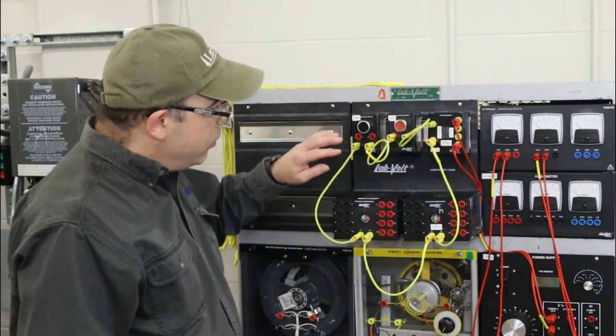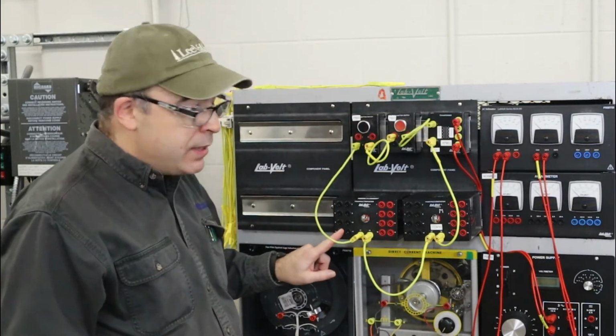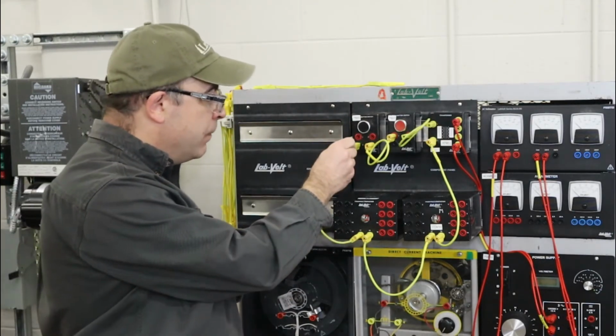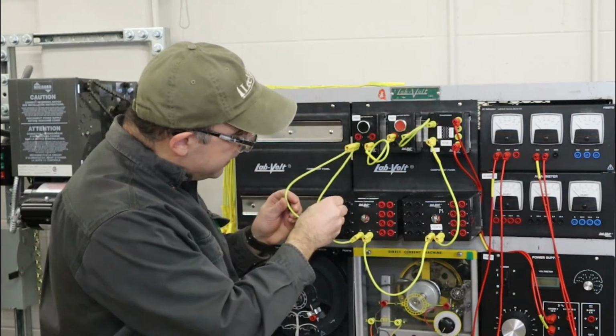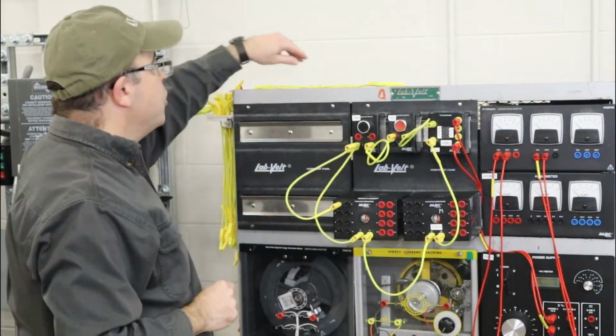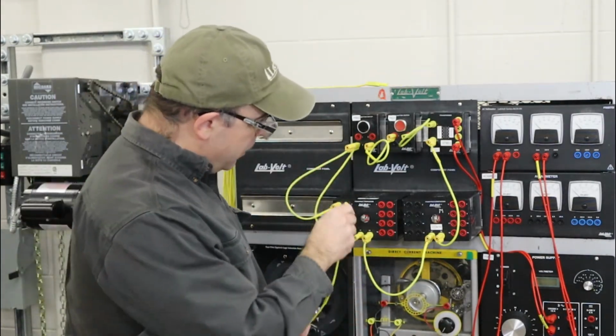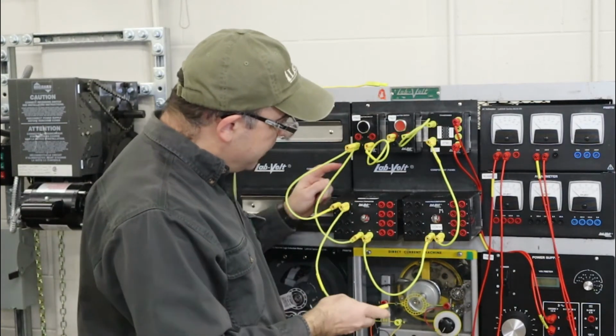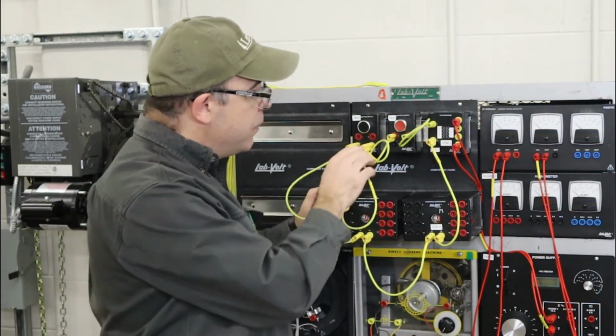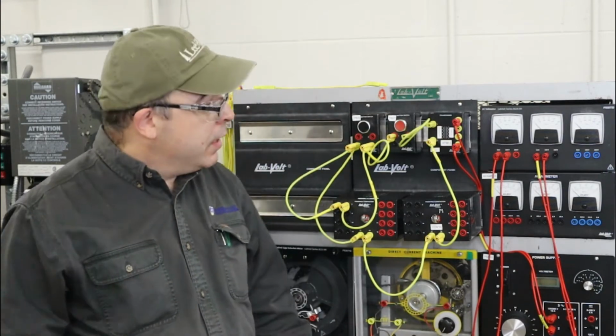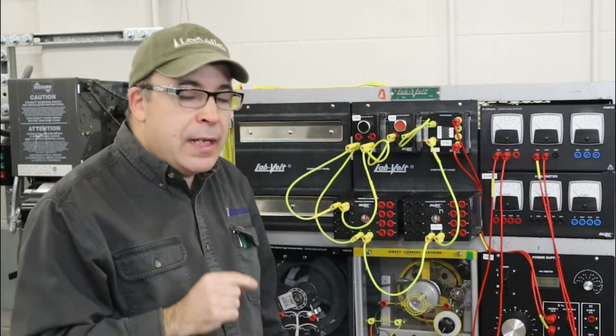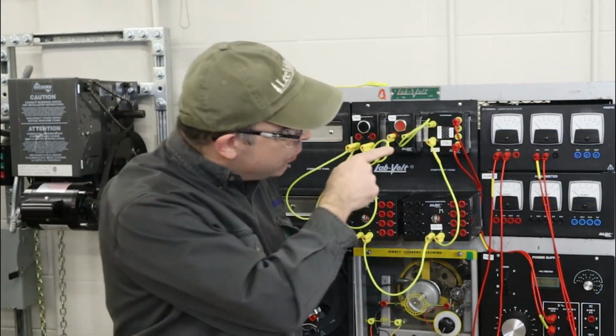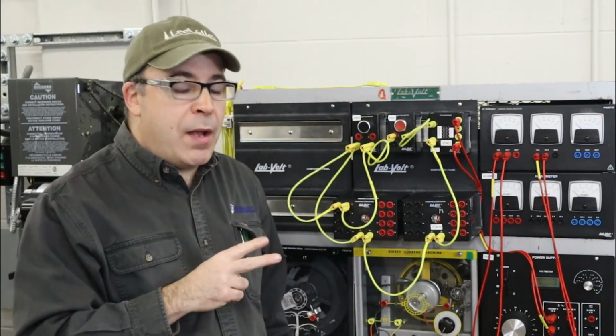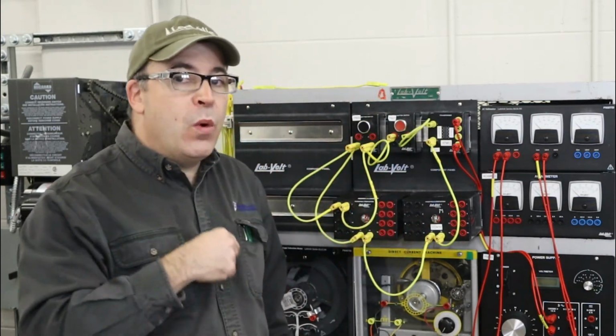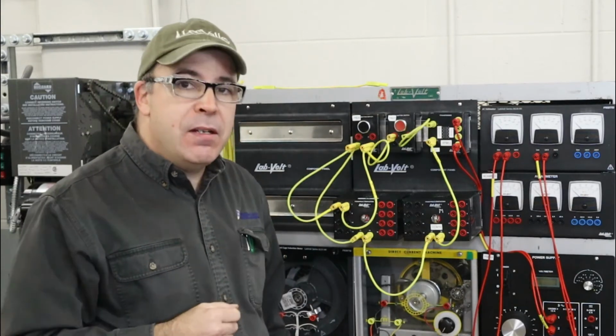Now, I could opt to put in the holding contact, and why don't we? So from one side of my start push button to one side of a contact, from the other side of this contact to the other side of the start push button. The only thing that remains now is I want to go and take voltage readings of the voltage drop across each of the coils when I energize this. So let's do that.